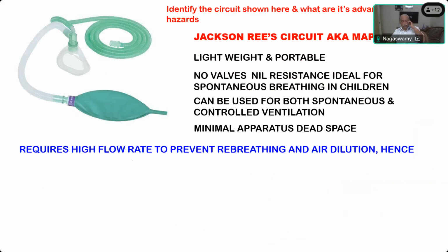Where will all the gases go in this circuit? There is no scavenging inside. If you don't use scavenging properly, you will be polluting the theater. And the gases that you are supplying to the patient, are they humidified? Is there any chance for humidifying the fresh gas flow that you are giving? No, sir, unless we put a filter separately. So it is mostly dry gases which you will supply.